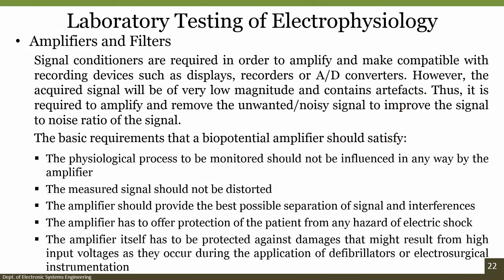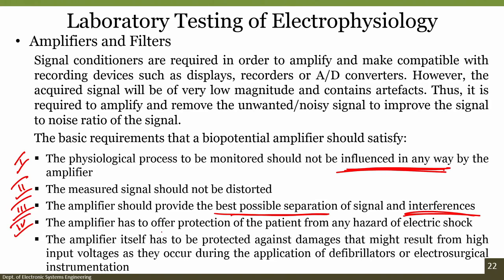So, what are the basic requirements that a biopotential amplifier should satisfy? The first requirement: the physiological process to be monitored should not be influenced in any way by the amplifier. So, you need to understand what kind of physiological process you are monitoring. Second, the measured signal should not be distorted. Third, the amplifier should provide the best possible separation of signals and interferences. That is why you generally use an instrumentation amplifier, right, a differential amplifier. Fourth, the amplifier has to offer protection of the patient from any hazardous electric shock, right. The patient should not feel any kind of electric shock whenever you attach your designed electronic module to the recording electrodes.